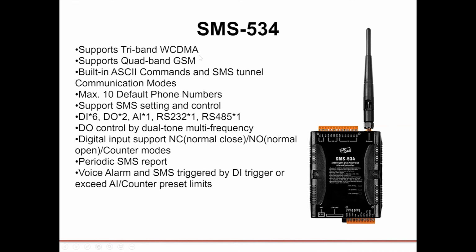And yes, this module supports tri-band WCDMA, quad-band GSM, ASCII commands, and SMS tunnel communication. This does have some local I/O: 6 digital inputs, 2 digital outputs, 1 analog input, and it communicates over RS-232 and RS-485. Like I said, you can control it with DTMF tones, so quite the handy and versatile alarm controller, very good for the outdoor application, or for the car park application that we described before.